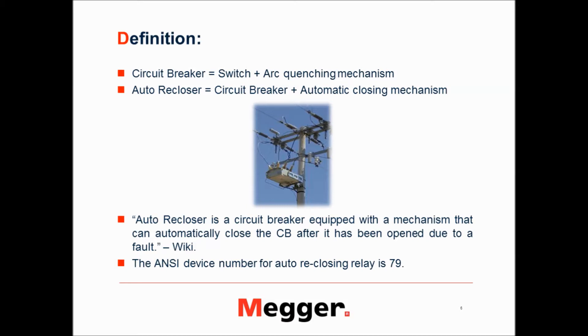The auto-recloser is nothing but a circuit breaker with an automatic closing mechanism. So according to Wikipedia, an auto-recloser is a circuit breaker equipped with a mechanism that can automatically close the circuit breaker after it has been opened due to a fault. Whenever there is a fault, the circuit breaker opens and isolates that part of the circuit, and the auto-reclosing mechanism will automatically close the circuit breaker and restore normal operation of the system. For those of you who don't know, the auto-recloser is represented by the ANSI number 79, so if I say 79, it means the protection function auto-reclose.